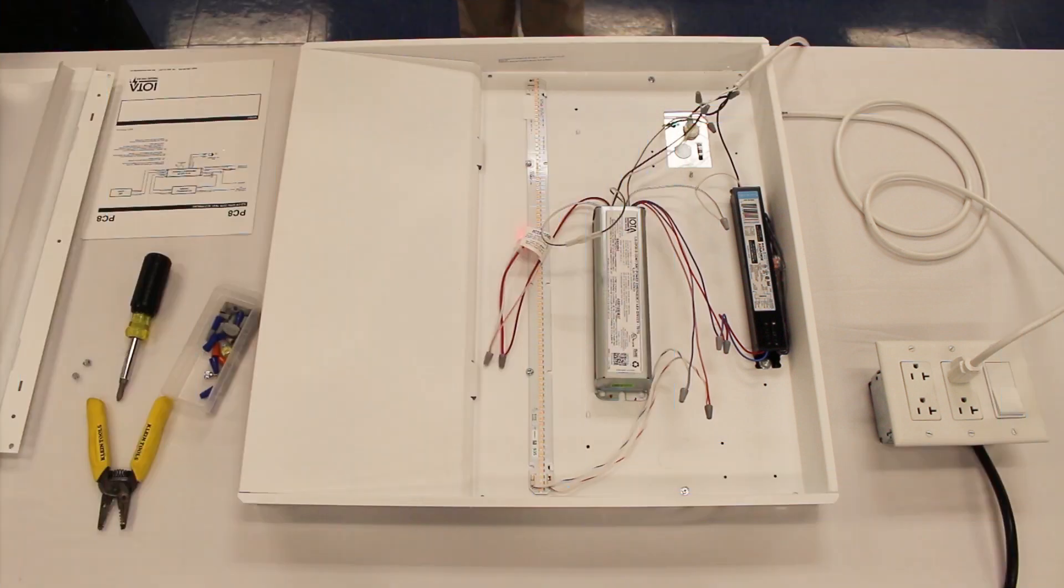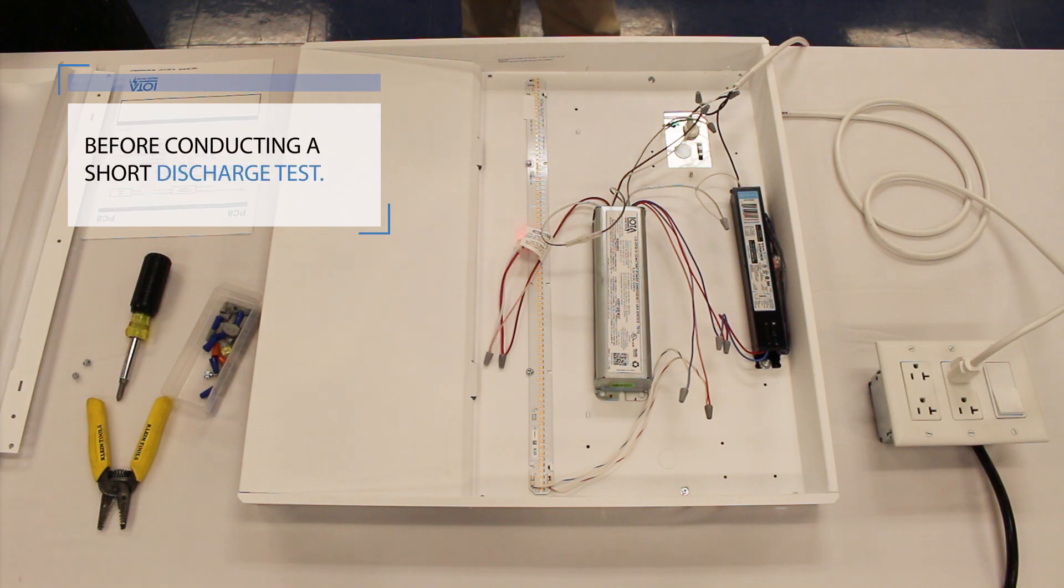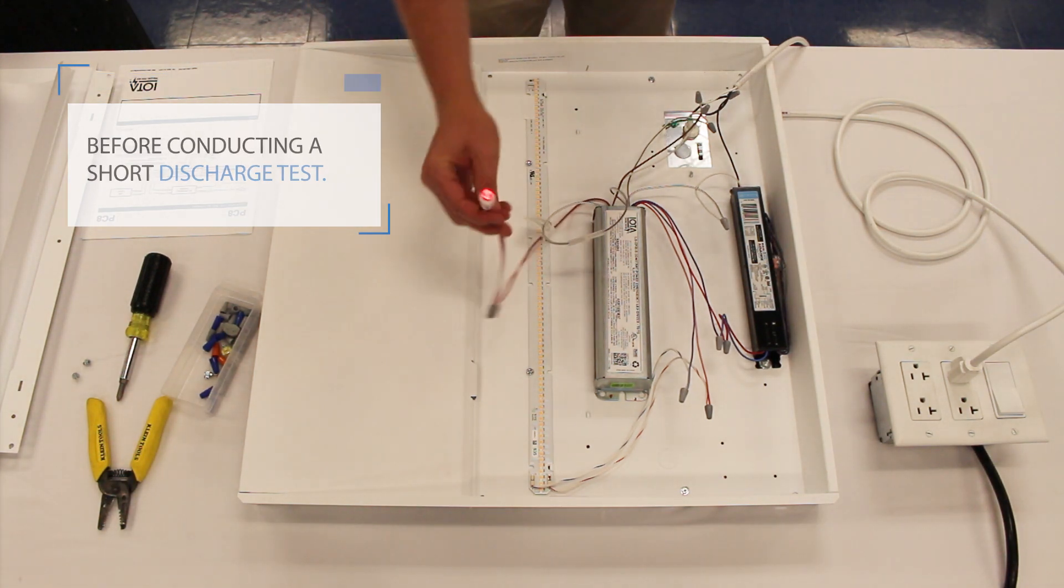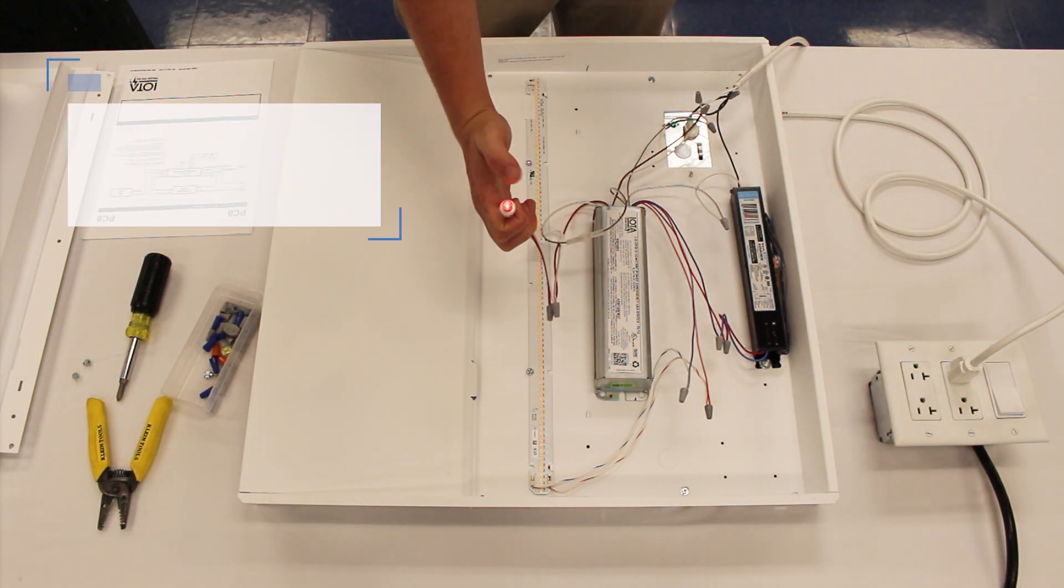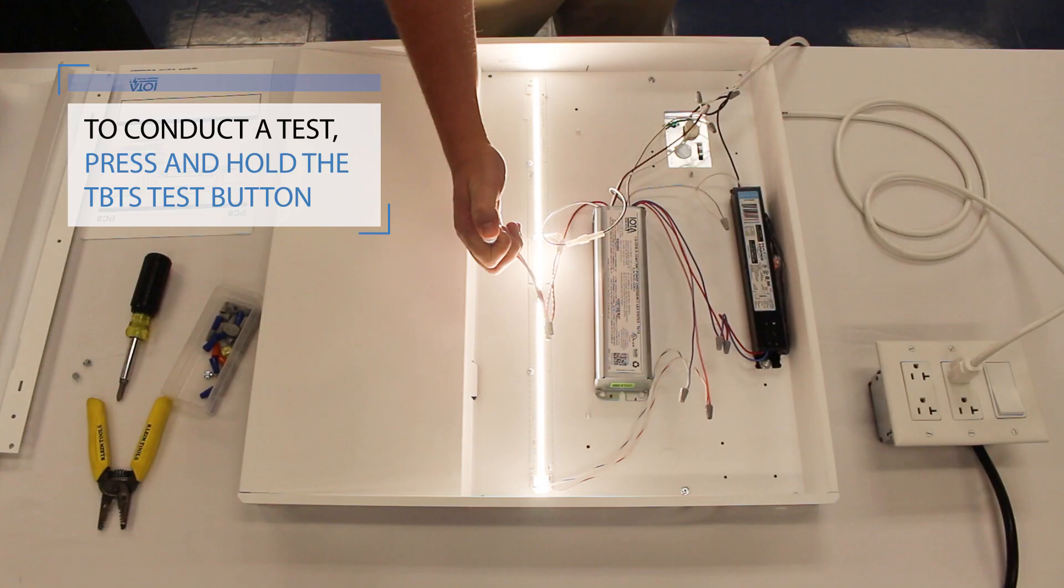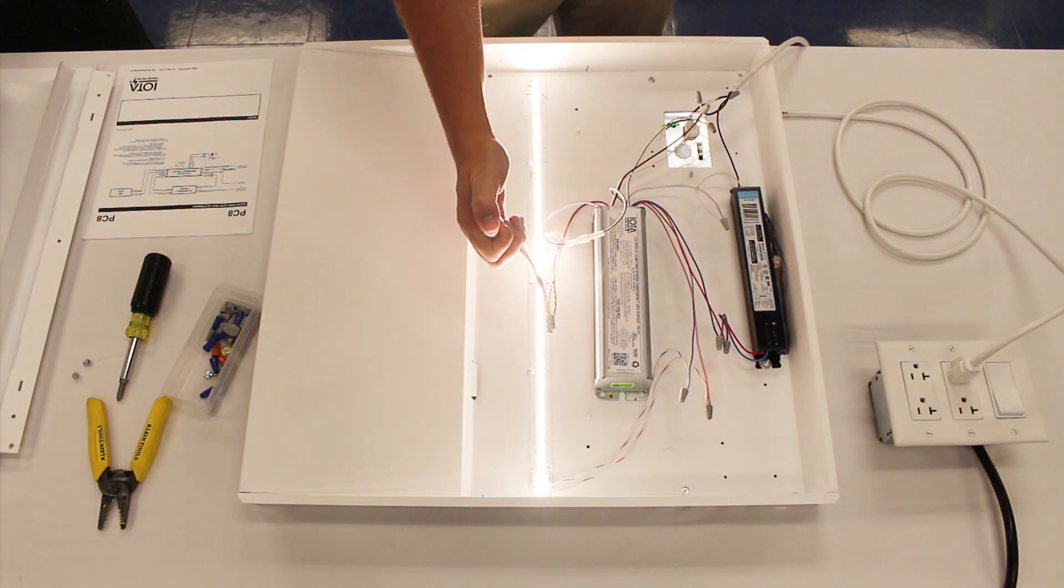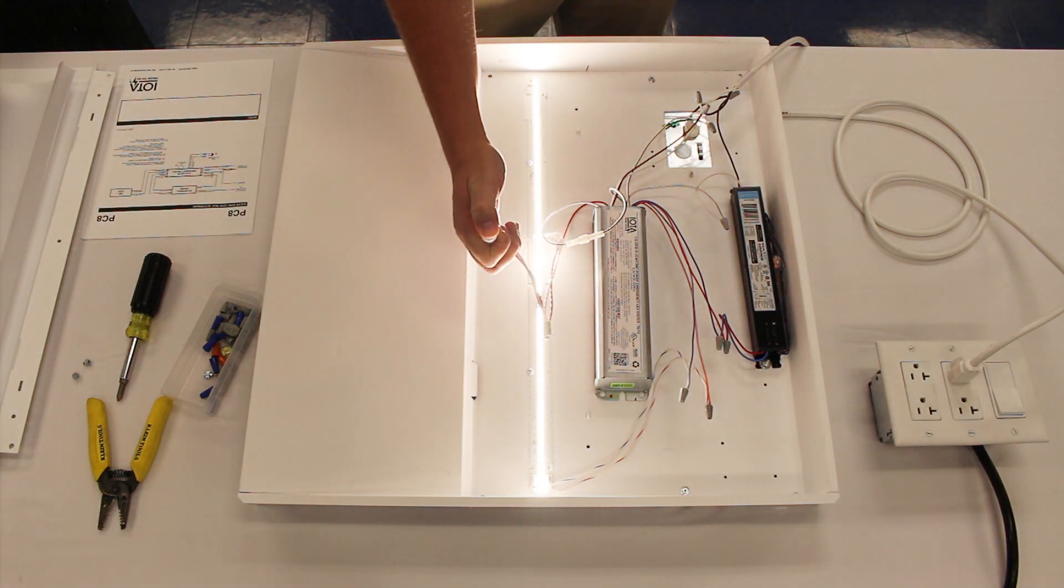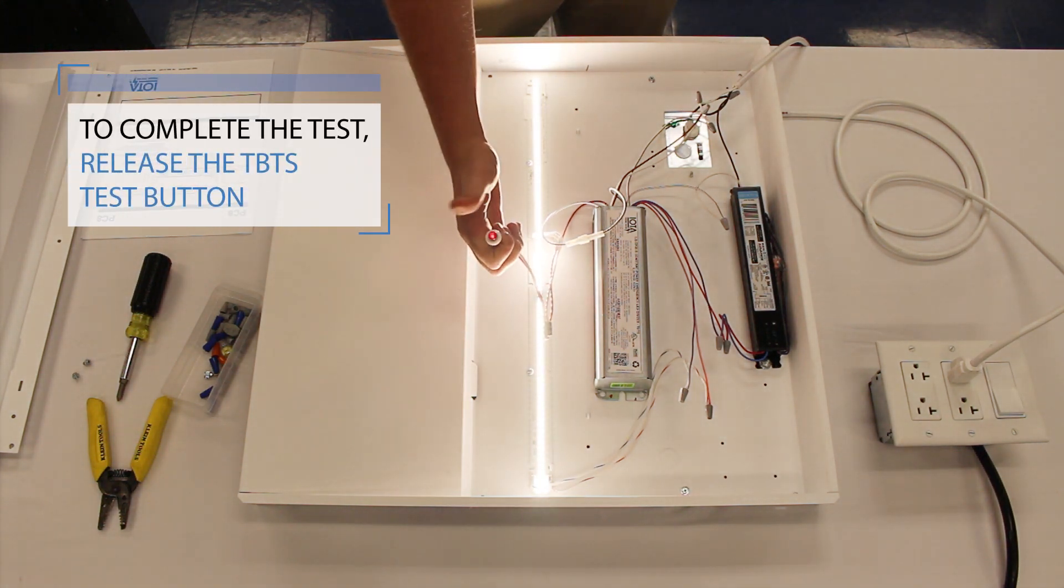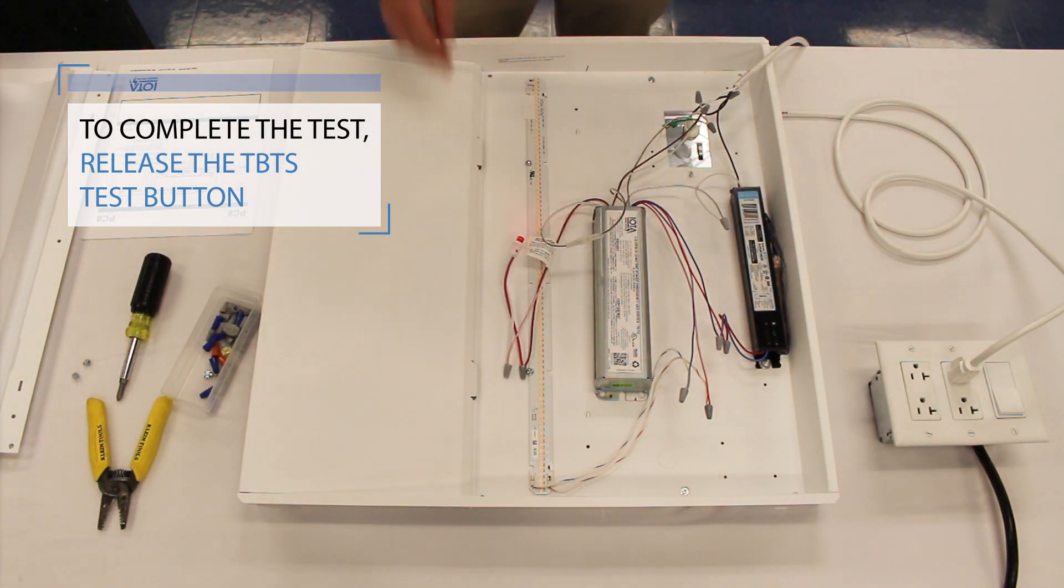After your ILB-CP LED emergency driver has been installed and wired correctly, allow the unit to charge for at least one hour before conducting a short discharge test. To conduct a test, press and hold the TBTS test switch. Your LED module should illuminate if it was switched off or remain illuminated if it was already on. To complete a test, release the test button. Your LED module should now return to its normal operation.